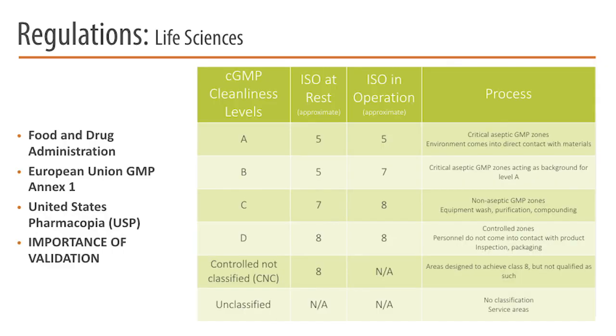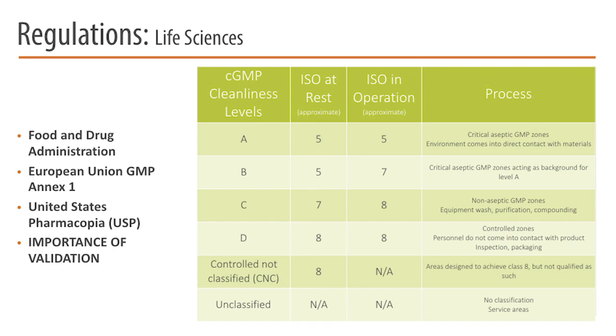And then when you get into the life sciences realm, there's the concept of CGMP, or Current Good Manufacturing Practices, which is basically an overlay of the ISO. I list the ISO at rest and the ISO cleanliness in operation as approximations. They're really not correlated one-to-one. But the cleanliness levels, A, B, C, D, controlled, not classified, unclassified, really stem out of the European Union GMP Annex 1. And that is an attempt to standardize nomenclature and standards globally, because a lot of the companies that deal in the pharmaceutical and biotech business are international companies. So we need to standardize that. So A being the most clean, these are for critical aseptic GMP zones. And also another thing I wanted to point out is that ISO typically deals with particulates.